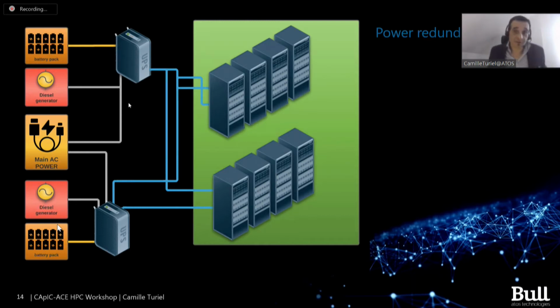So for all these reasons, a performant UPS, and I would say definitely an online interactive UPS, internally never puts a load in front of the main AC. So even when in nominal working condition, you are never directly coupled with AC, neither with the generator nor the AC power. So the UPS also acts as a filter. It will convert the AC power to DC, and from DC it will reinvert it to recreate a proper pure sine wave current.